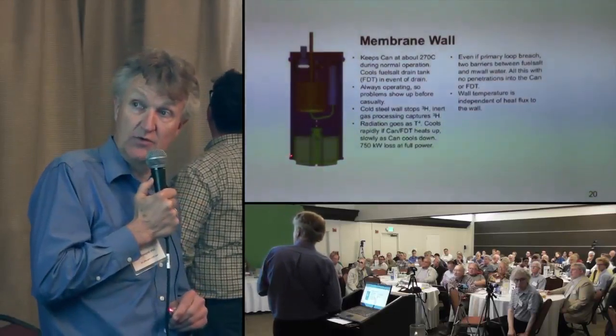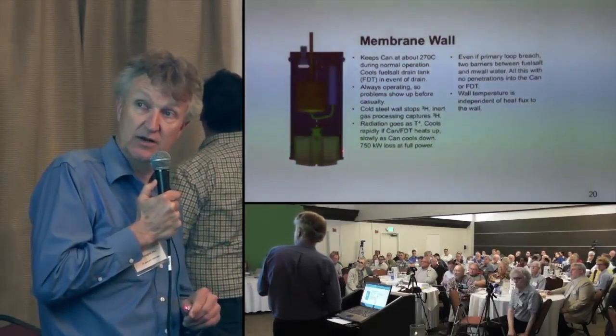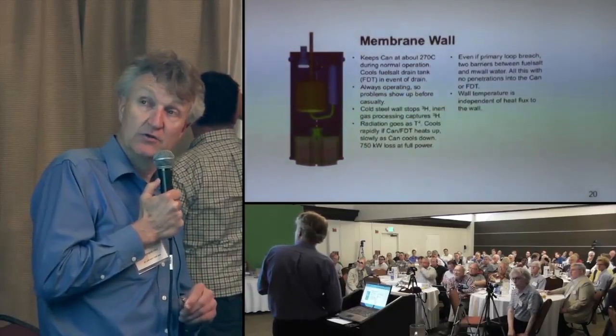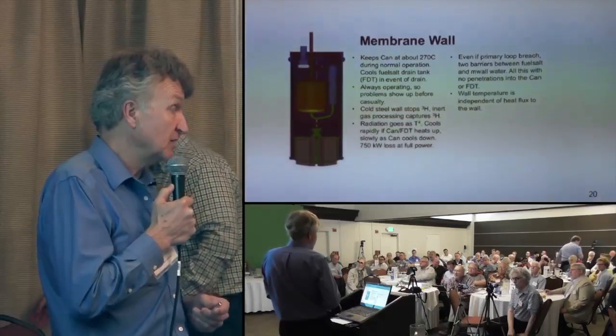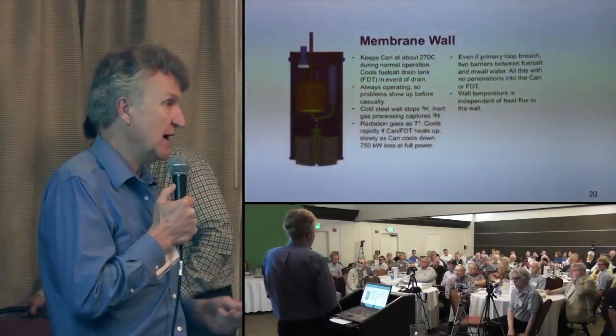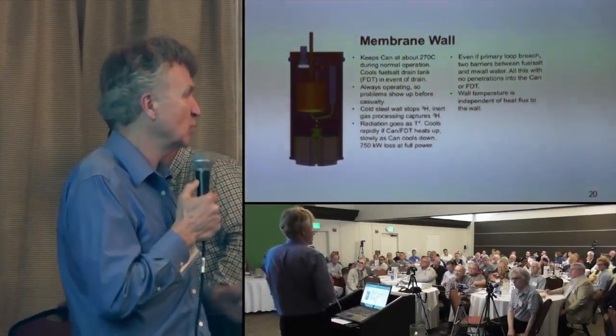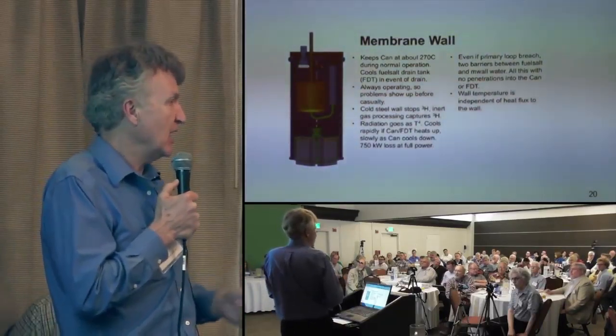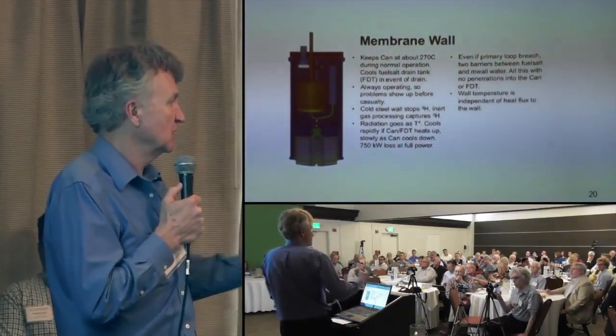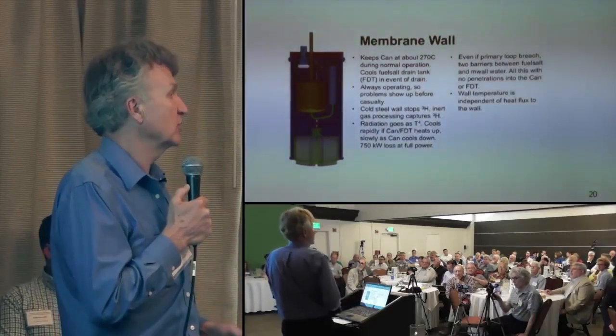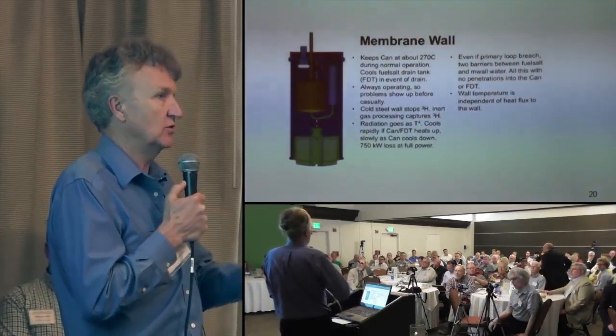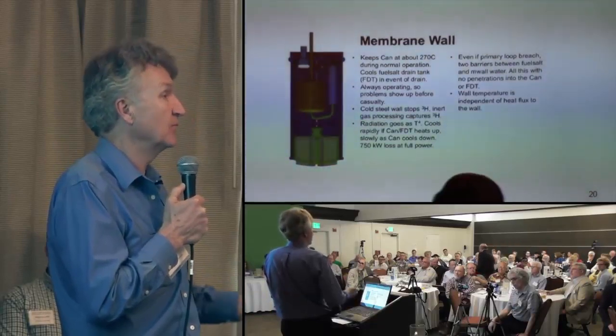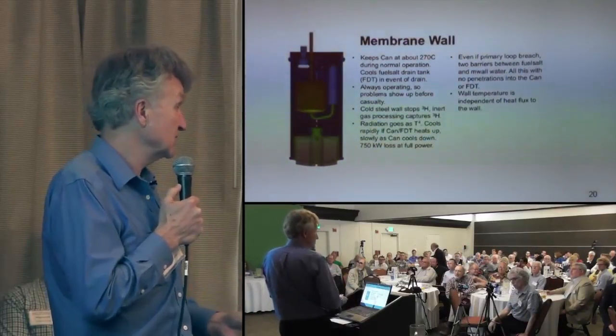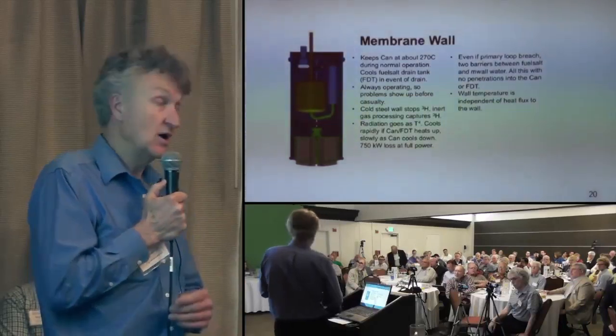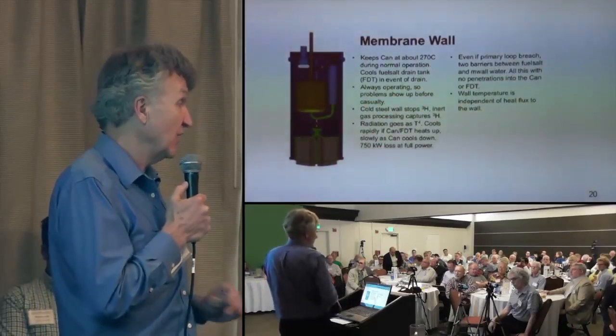And likewise, if you get down to the fuel dump tank, if we have heat generated down here, then it'll pump up from here. So the decay heat removal is there all the time. It's operating all the time. If something should happen, some earthquake squeezed a pipe or something that blocked it, we will know because we see it in the flow during normal operation. We don't have to wait for the tsunami to hit to discover we have a problem. So we have it continuously being tested, continuously running, and the operator has no valve, nothing he can do to stop it.